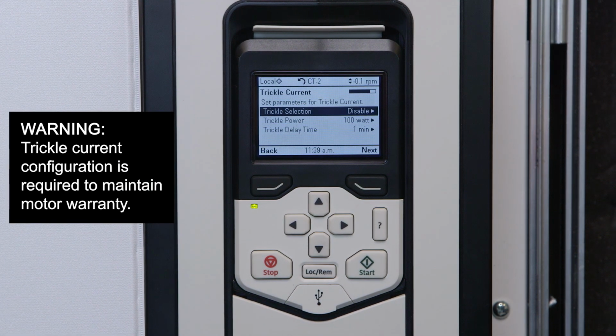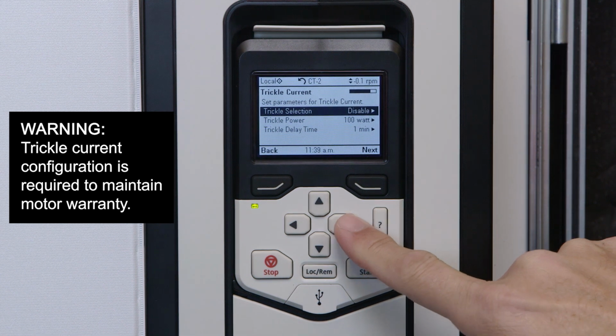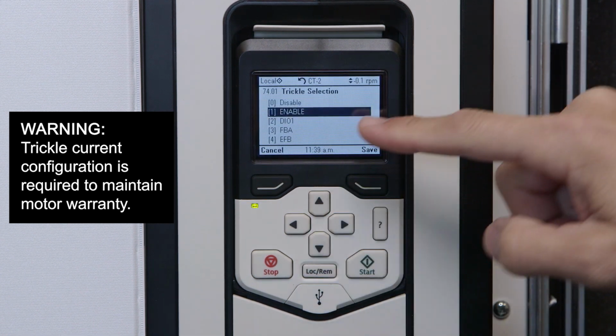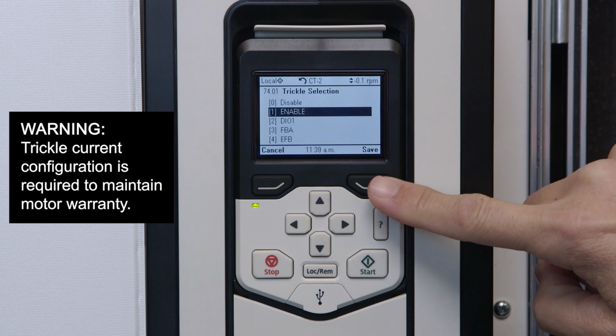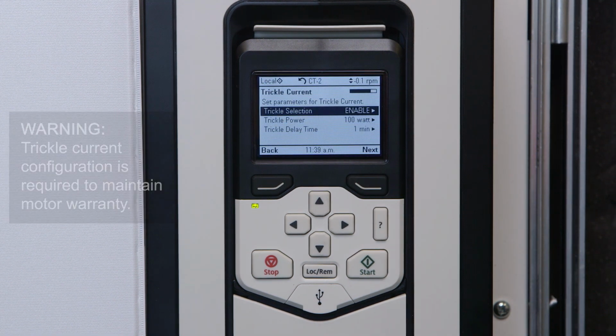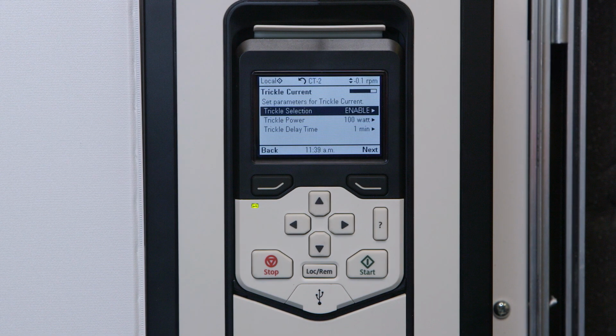Now, use the right arrow to enable trickle current. Remember that if the trickle current is not properly configured, the motor warranty is not valid. Let's configure the trickle current power. The trickle current provides a small amount of power to the motor windings when not running. This prevents condensation from forming inside the motor. The power setting of the trickle current is based on motor frame size.